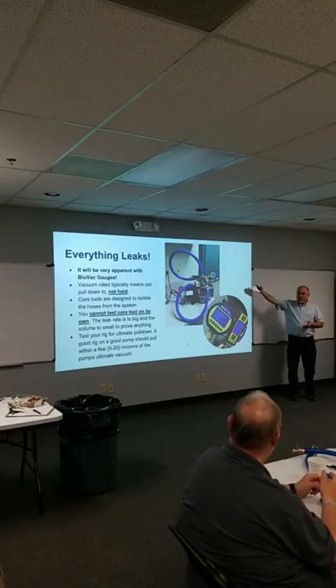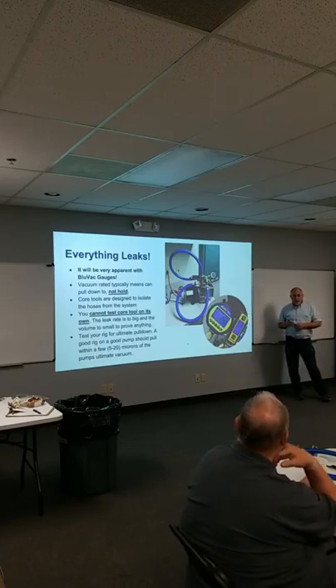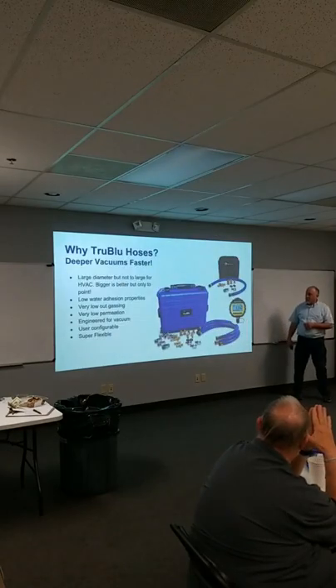So what I wanna make sure is that when I hook up my hoses here, I don't have significant losses on my pump. Typically, if I say my pump will pull down to 50, then my hose should go down to no less than 100. If my pump will pull down to 25, I wanna see my hose get down to 50. If my pump will pull down to 10, I wanna be down at 20. This pump will pull down around 19, 20 microns, and I'm down at 24 microns here eventually, okay? But that's how we test the rig.